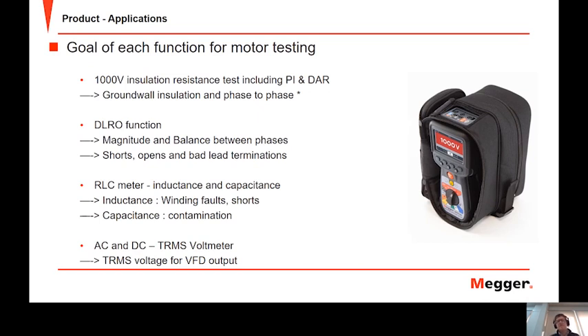So the goal of each function of the MTR: what are we really looking to find with each test? The IR suite of tests will check the ground wall insulation, and it can also be used for the phase-to-phase insulation. But again, to check phase-to-phase, you have to be able to open the neutral point of the motor. So we're looking for contamination and things like that as well.